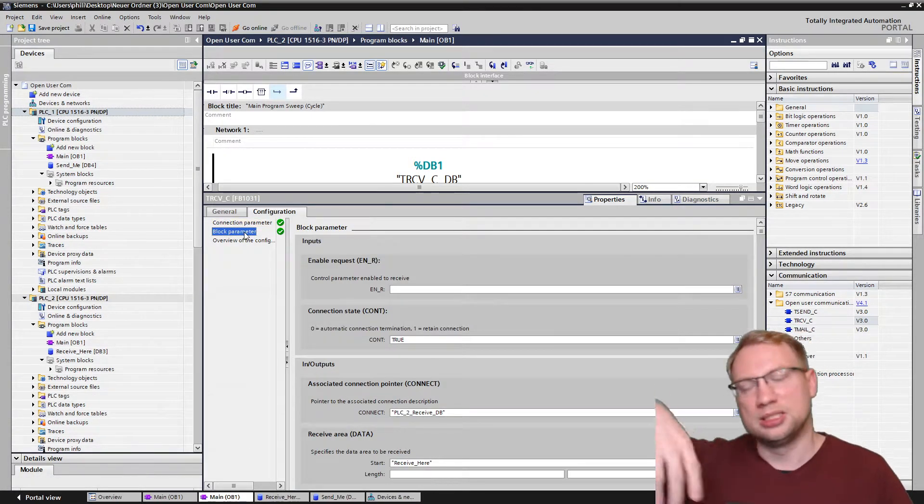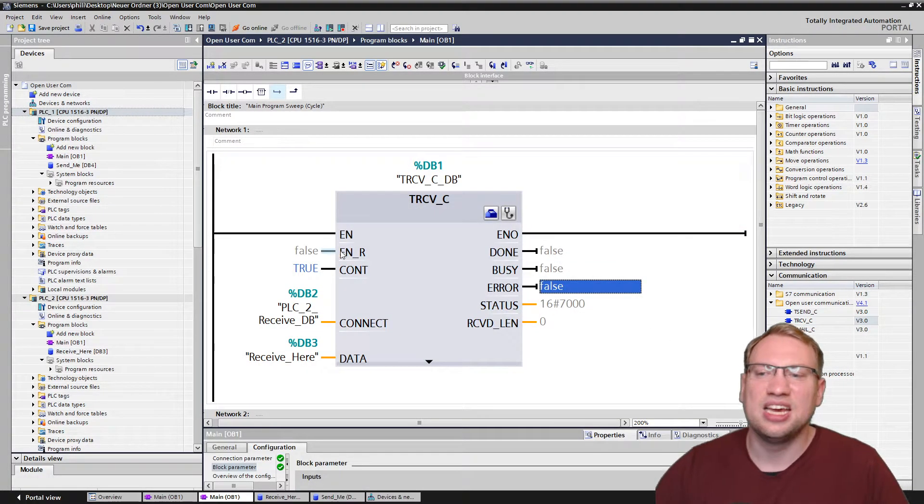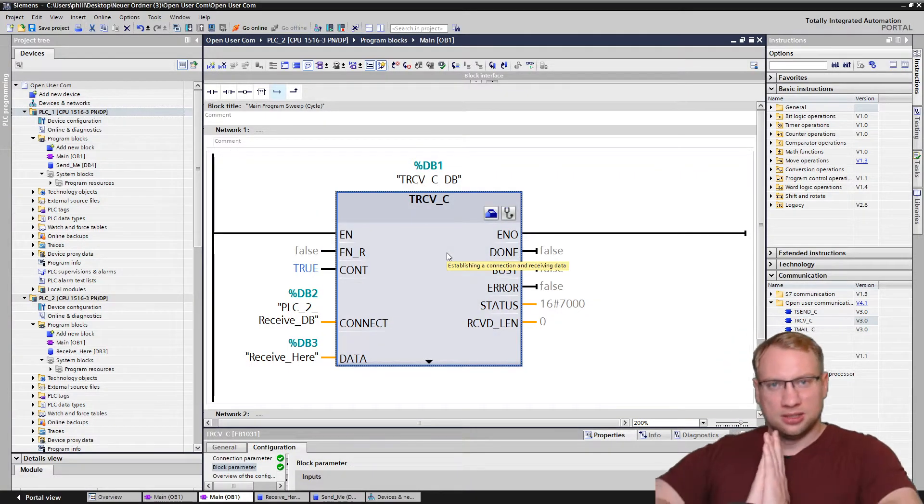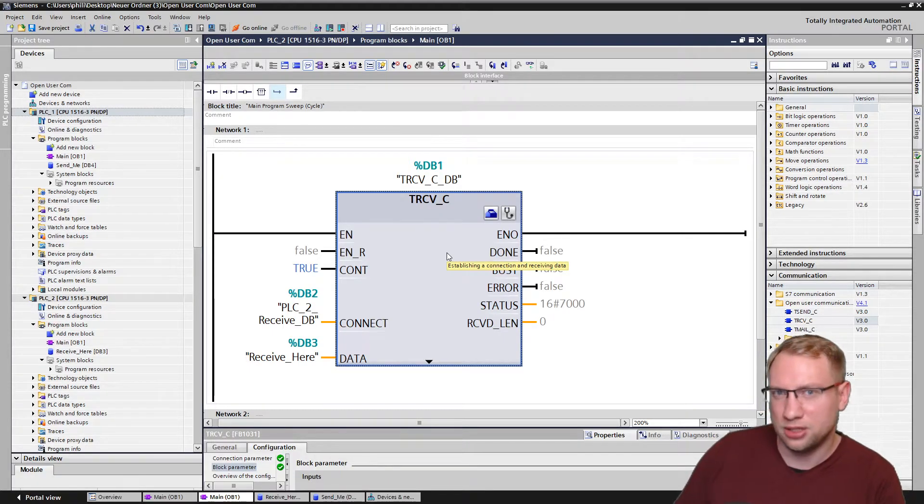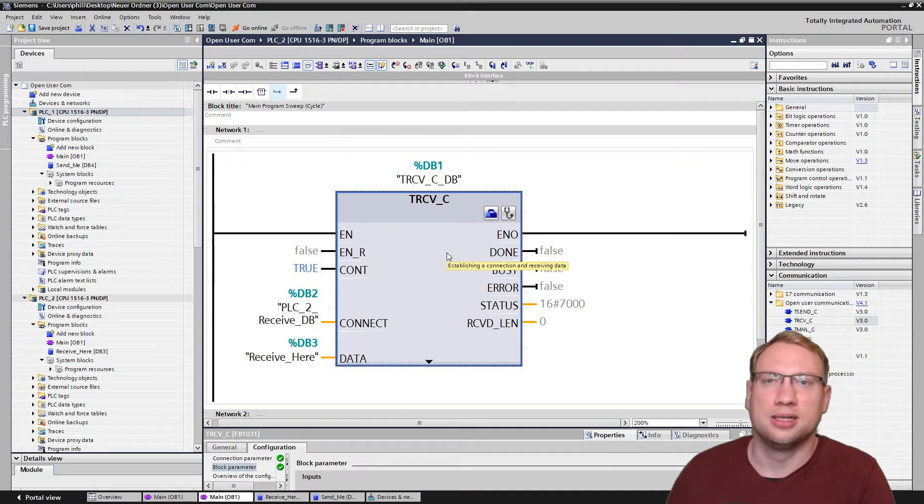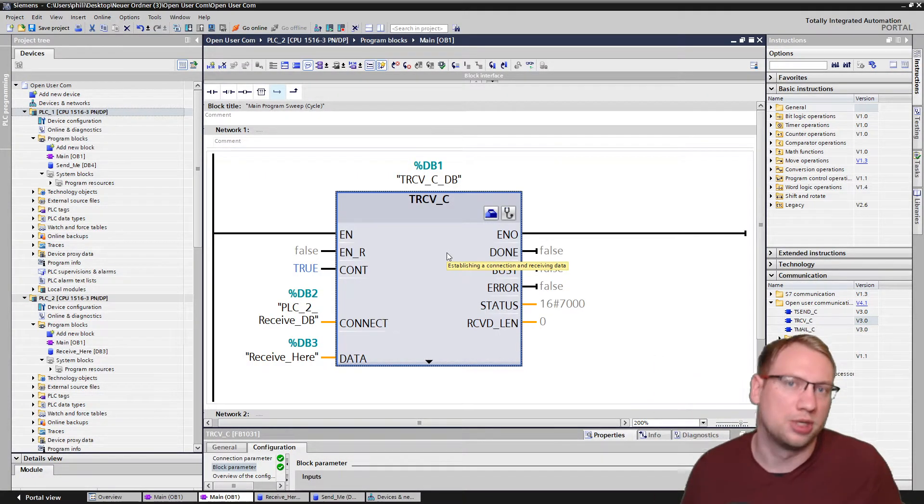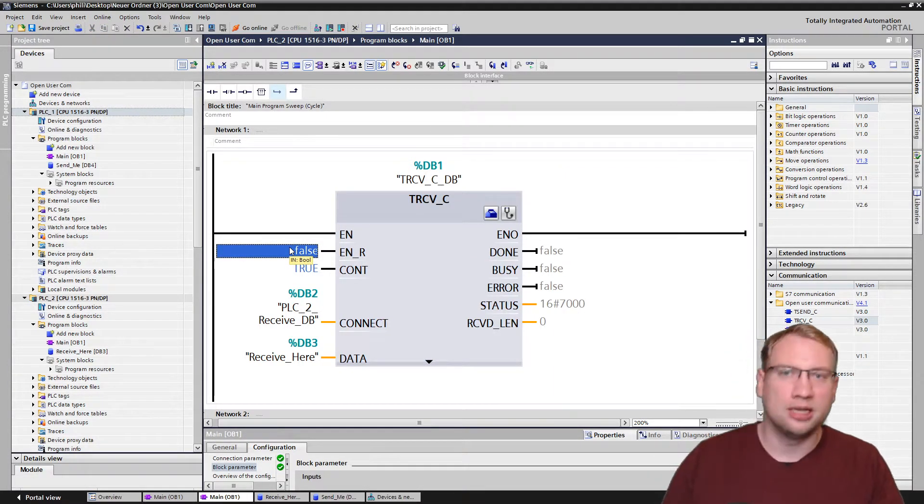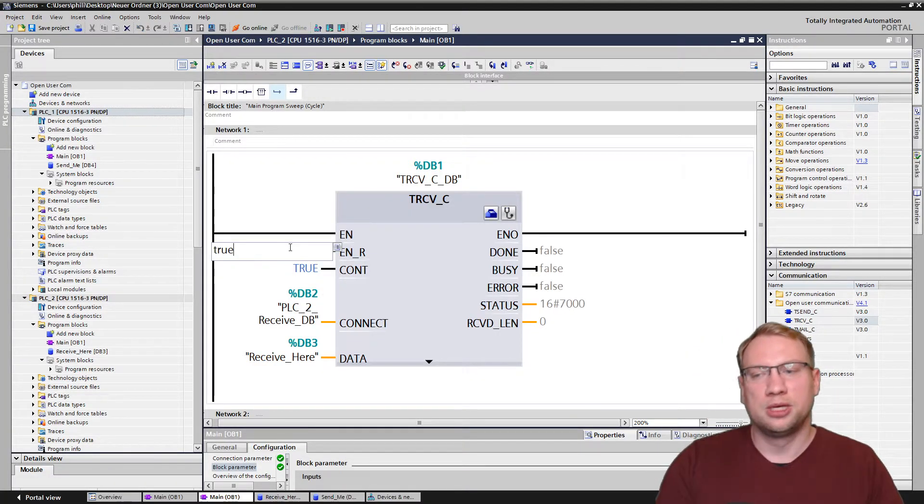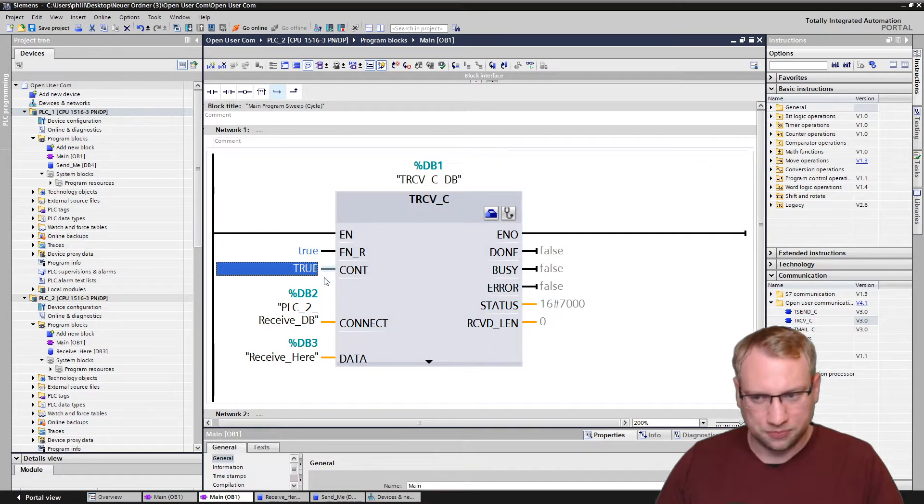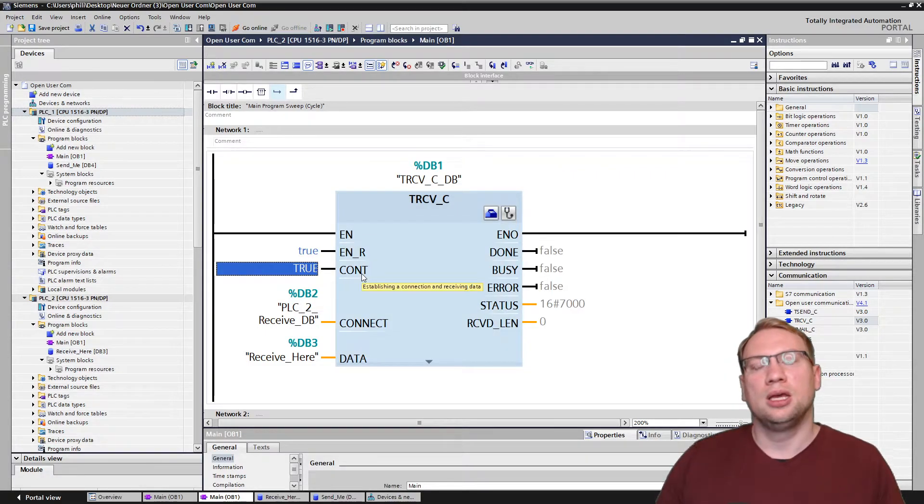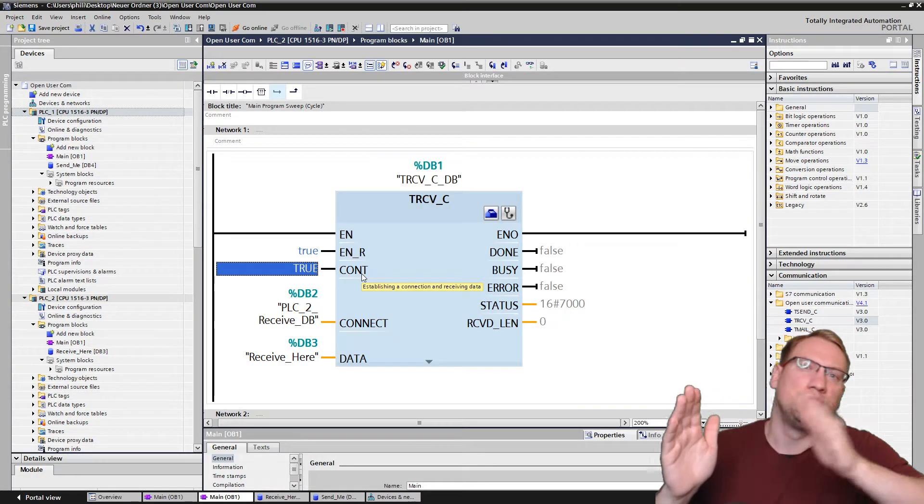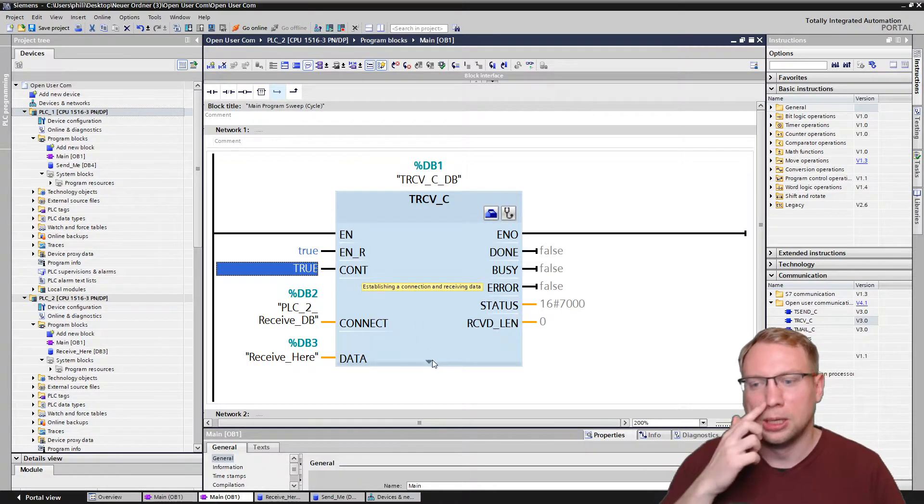Block parameters, now it's green. The last thing that's missing on here is this EN_R. Your PLC does not always want to receive. You can tell your program, you can tell your PLC when it should receive. It could be a switch that you allow the reception of data. It could be like you could put password protection on there or something like this. In my case, I want none of that. I just want this to be true. It's true that we can always receive data. If this is true, I can always receive data. CONT, you see CONT showed up here. CONT is also true by default. CONT means if you have a connection once, keep it up. Don't disconnect and reconnect for the next time. Just keep it up because more data is coming in. That's the CONT.